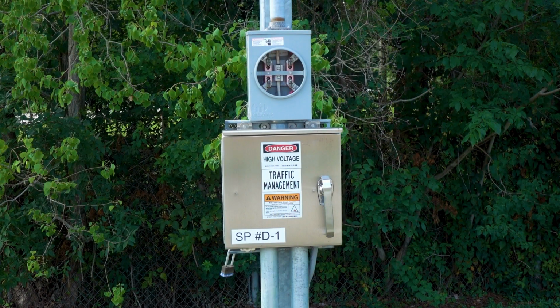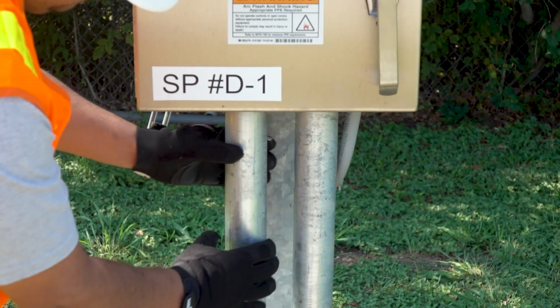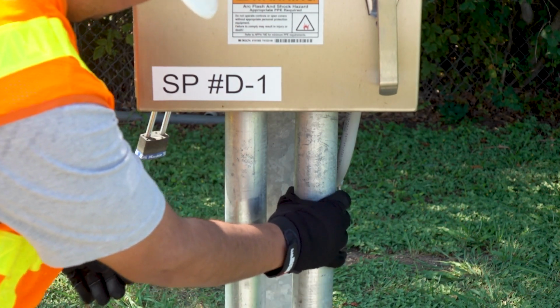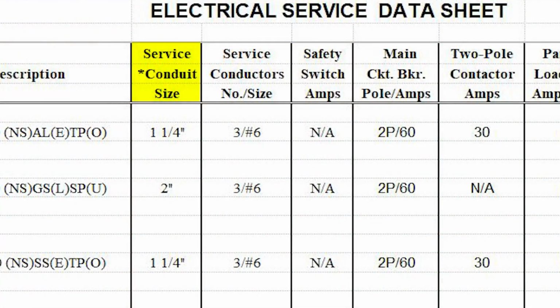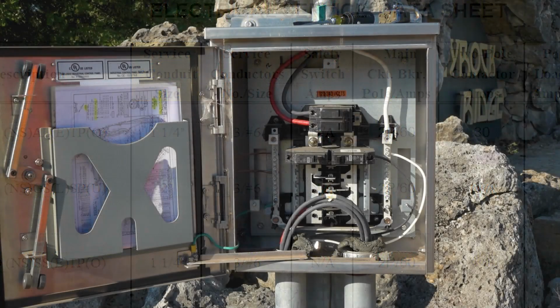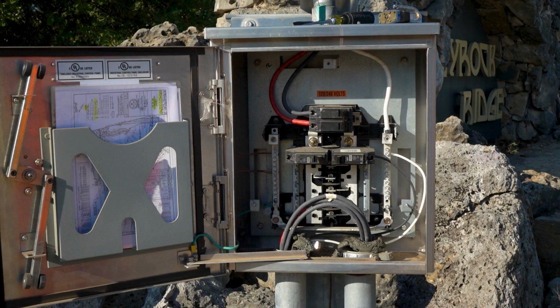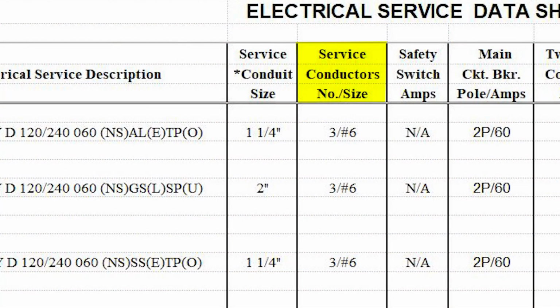When the service descriptive code has the letter U in the last spot of the code, the service conductors connecting to the utility company transformer are to be routed underground. These conductors are called the underground service laterals. The size of the conduit, either above ground at the service support structure or underground, will be as called for on the plans. The inspector must confirm that the correct material type and size was installed. The size of the conduit is shown on the electrical service data chart for that service's location in the plan set. The required size of the conductors contained in either the underground service lateral or the service entrance conduit can be determined from the service data chart in the plan set.